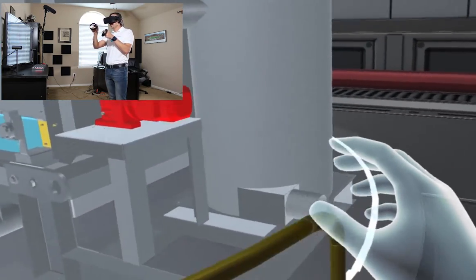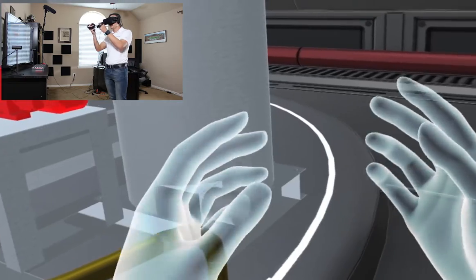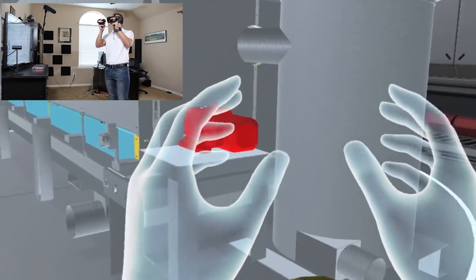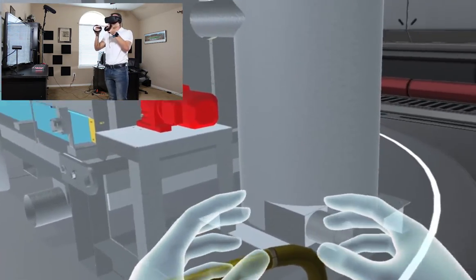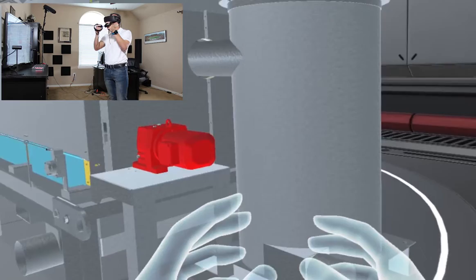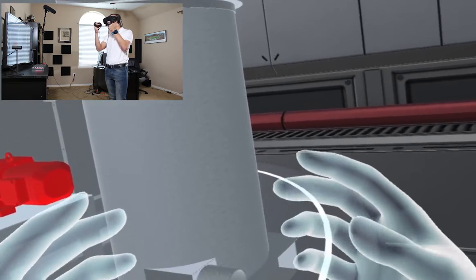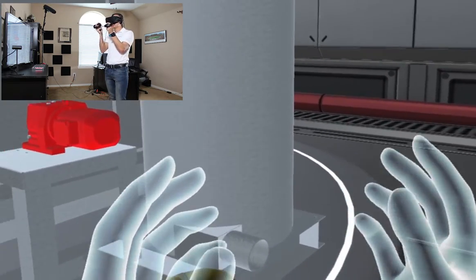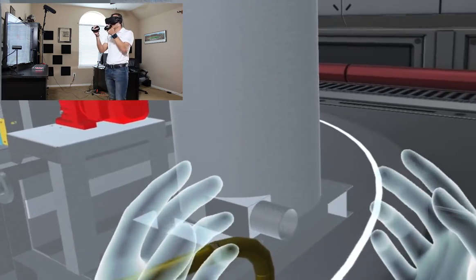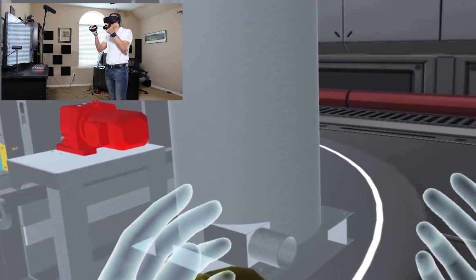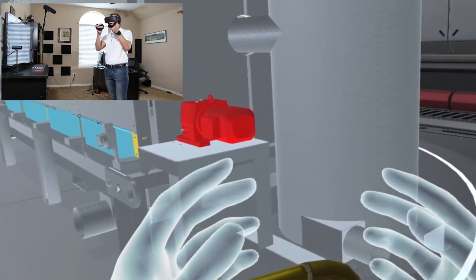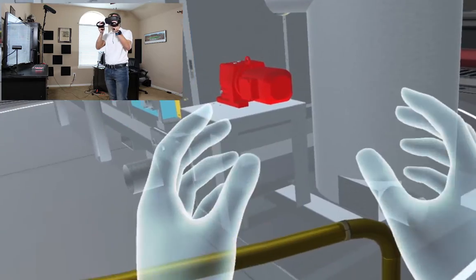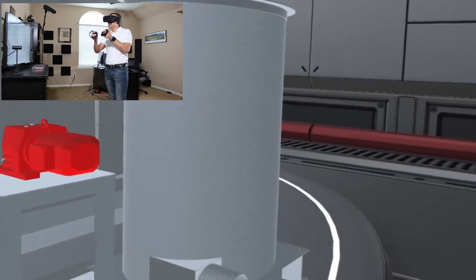As sludge comes into the system, whether it's coming off of a biological system or even primary sludge, it can't be thickened as is. We have to add a polymer, and that polymer is really the majority of the life cycle cost of owning a thickener. It's around 80 to 90% of the entire life cycle cost versus the capital requirement of the thickener itself.